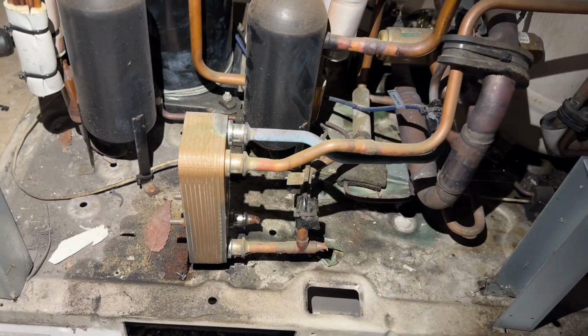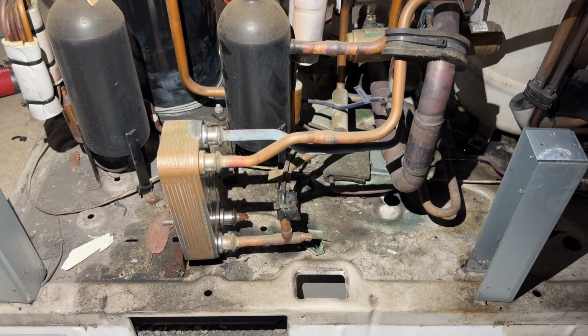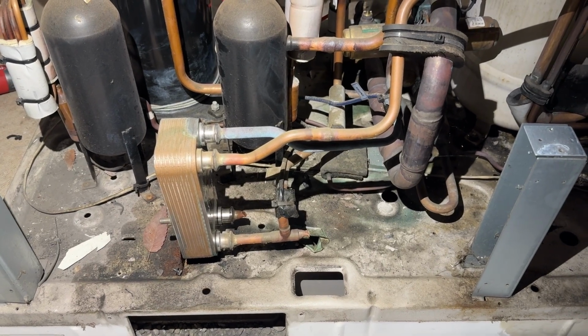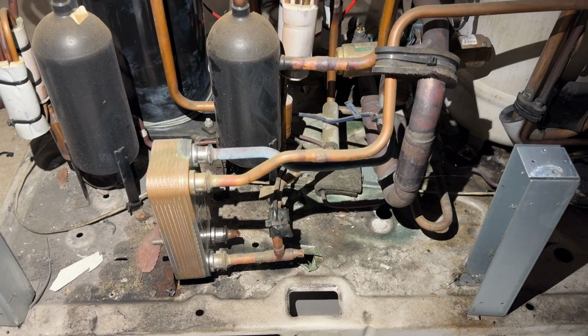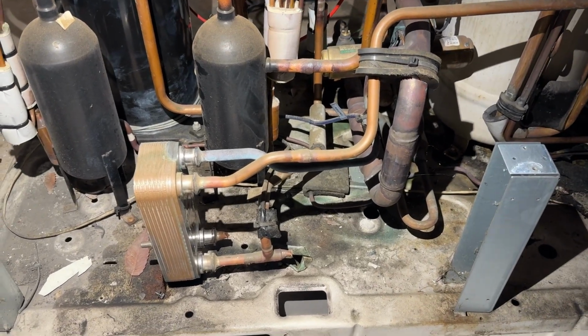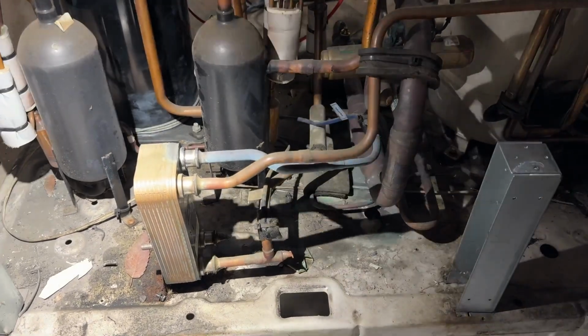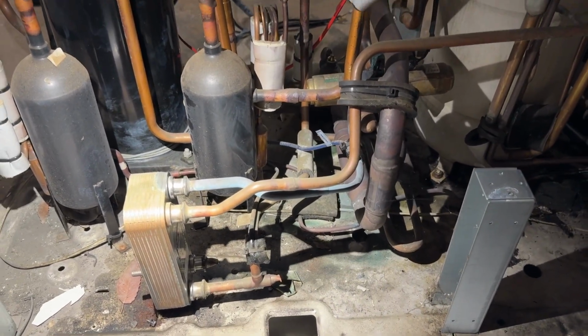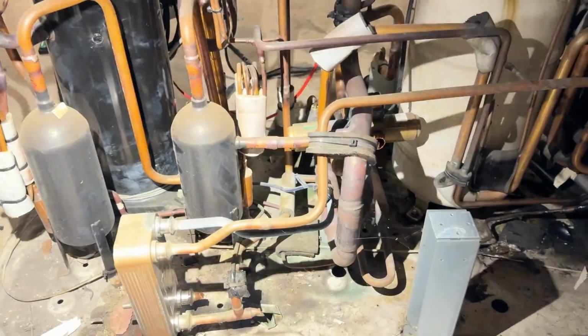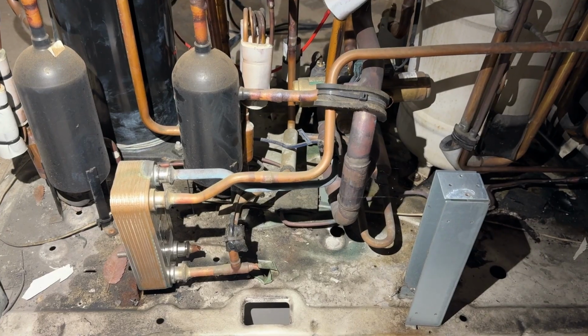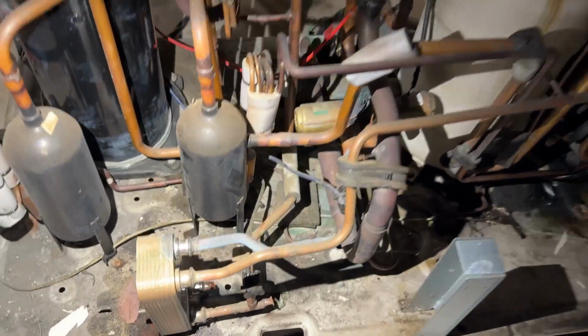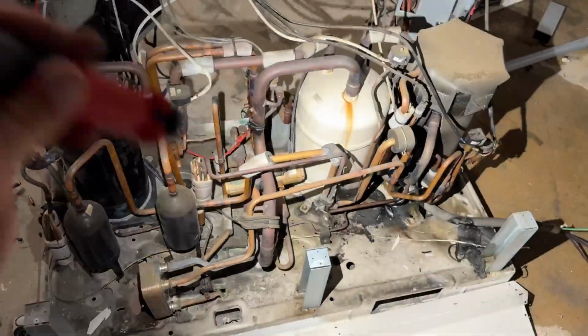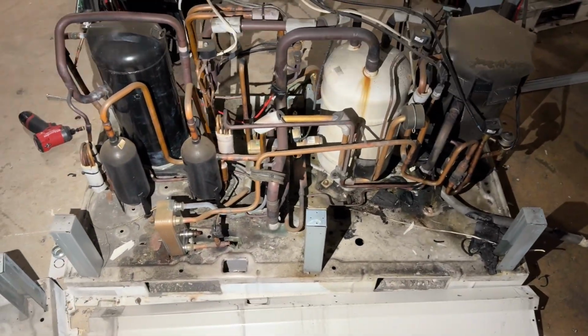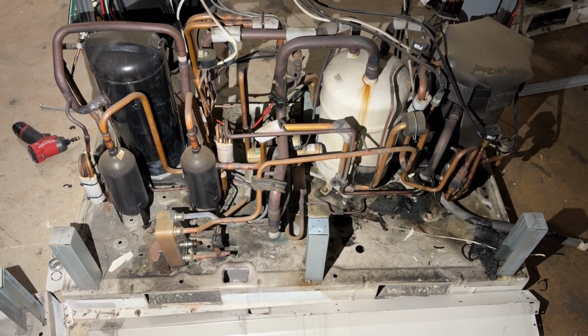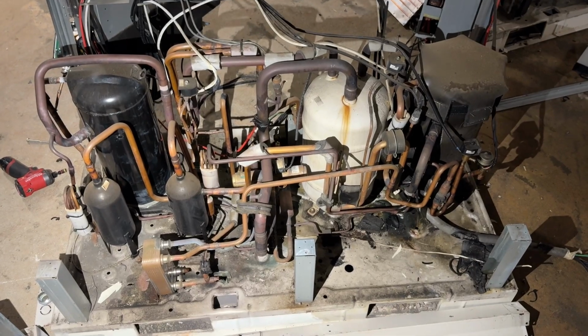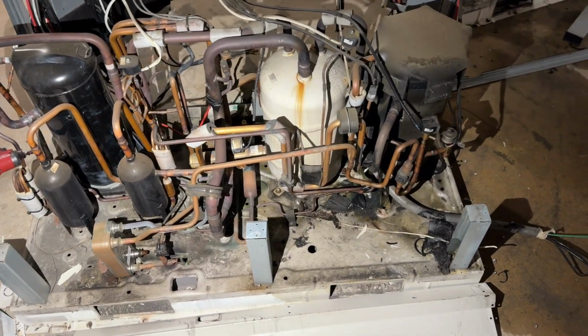This is the subcooler. And see, in cases where you have like a few units cooling and then a few units heating, those heating units are stealing liquid. So what this can do is subcool the refrigerant further than what it is subcooled by the coil, and it can then feed the indoor units, okay? And that's why these things are tricky to work on refrigerant-wise, besides all this crap, is because they can run just fine on half charge, besides the compressors being overly taxed. But as far as performance, you could take half the charge out and they do just fine.